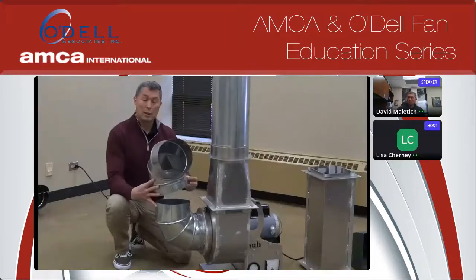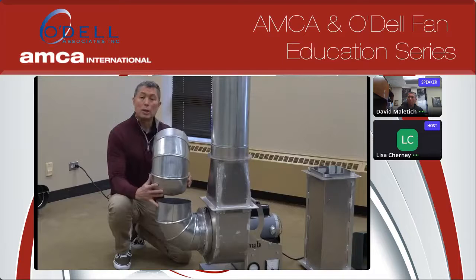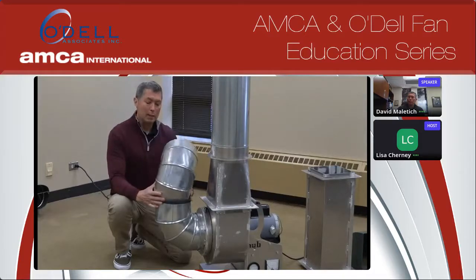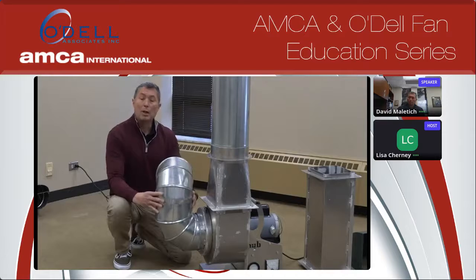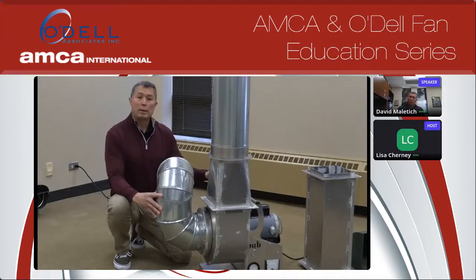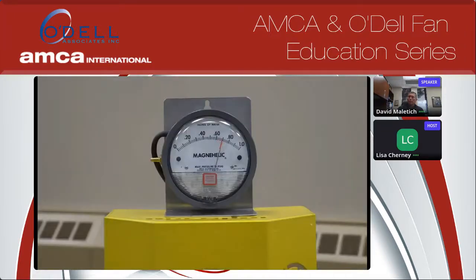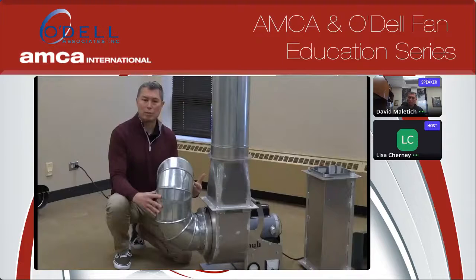Now when I turn this 180 degrees, listen to what's happening. I put it on here, the fan gets much noisier, sounds a little bit rougher, and also the Magnehelic is showing the pressure went up as the fan's operating. So that extra noise is basically because we're now counter-spinning the air as it enters the fan. Air is going in the opposite direction of the wheel rotation, kind of like when you're rolling down the driveway backwards, put your car into gear, push it forward, it effectively moves, but it does it in a very rough manner. Same thing happens with the air as it enters and discharges the fan.